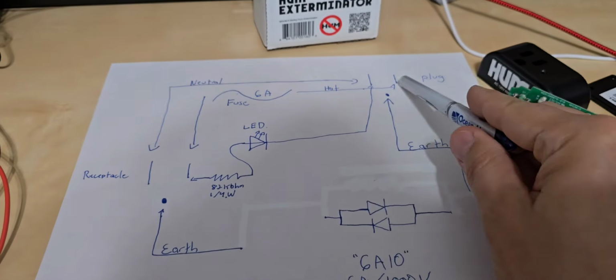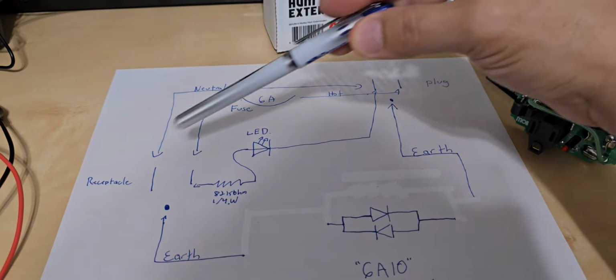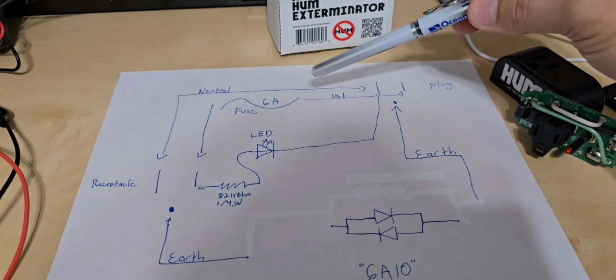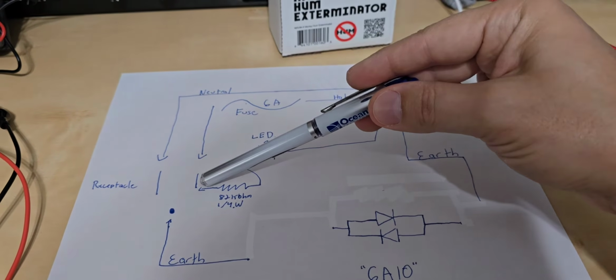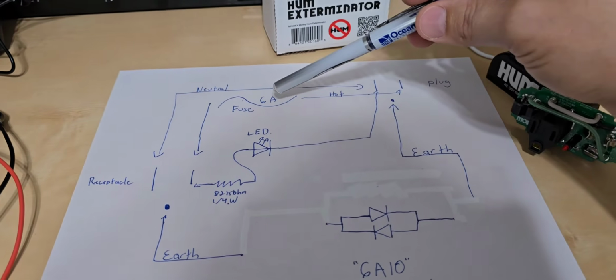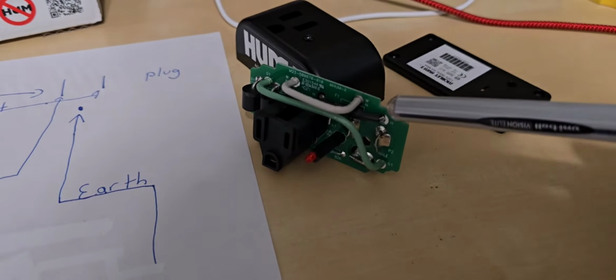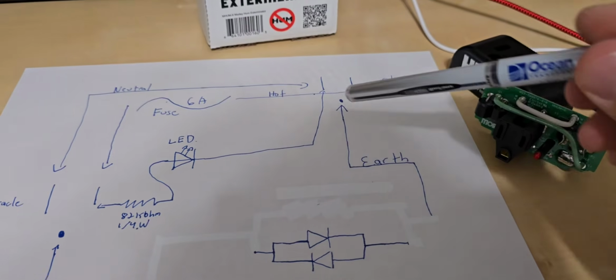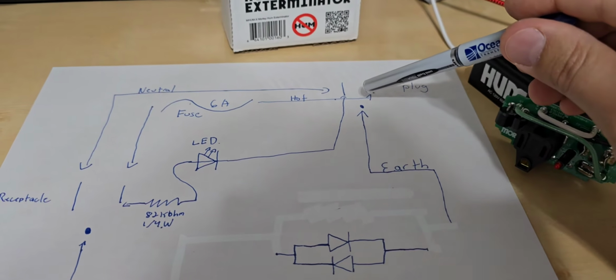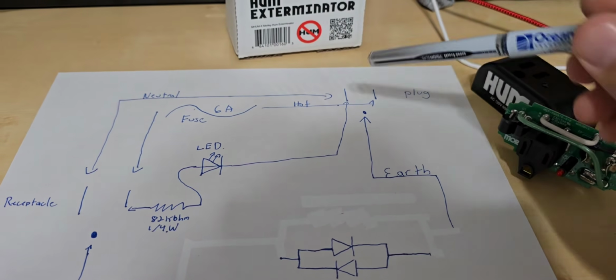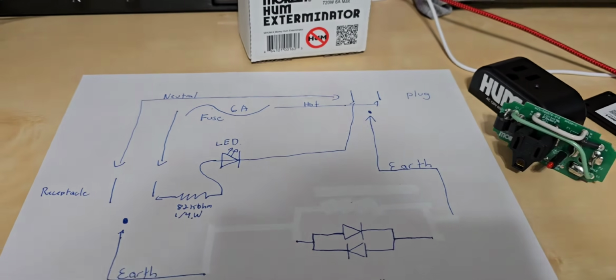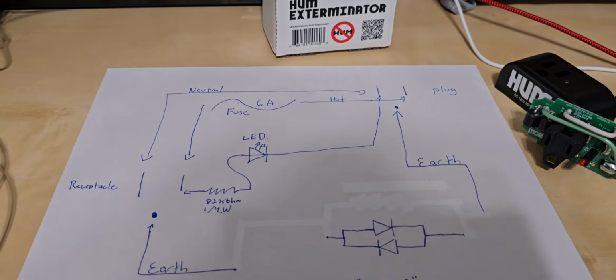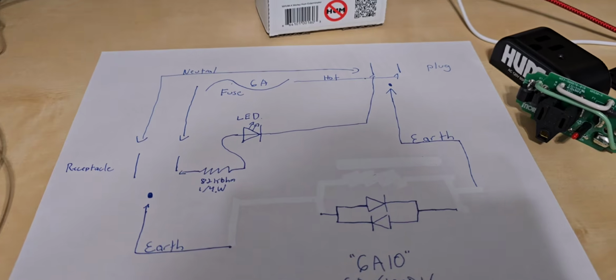The neutral is passed between the receptacle and the plug without anything in between. On the hot side, we have from the receptacle through a 6-amp fuse, right here, and that goes over to the hot pin of the plug. That makes sense—so you're limited to 720 watts, or 6 amps of current at 120 volts.